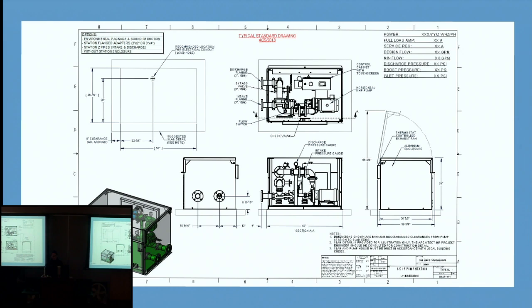And when the contractor installs this pump, usually that's when the pump manufacturer will be out there to help with the installation. If the pump manufacturer doesn't come out, then when you go to do your water coverage test, just call the manufacturer of the pump and tell them a couple of days ahead of time that you're doing the water coverage and you want to make sure that the pump is working per specifications. The pumps are, as I said, complicated, and when you do have one, like I showed in one of the first slides, it's downstream of your backflow. It can't be upstream of your backflow.